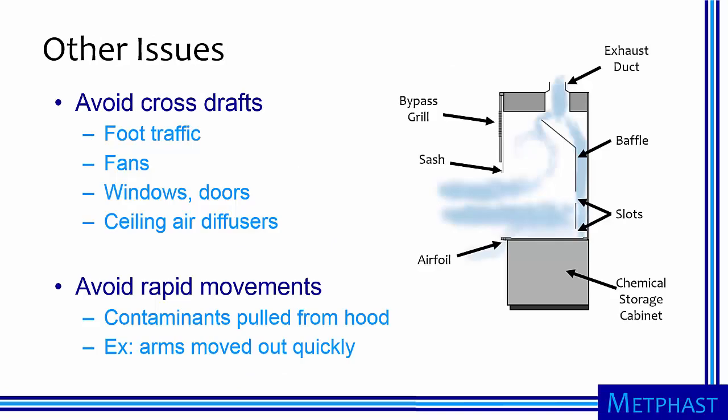In addition, when using a chemical fume hood, avoid cross drafts such as those from foot traffic, fans, windows, doors, or ceiling air diffusers. Drafts can dramatically change airflow patterns and cause contaminants to escape capture and enter the room. Also avoid rapid movements such as rapidly pulling your arms out of the hood, as such actions can also change airflow patterns, allowing contaminants to enter the room.